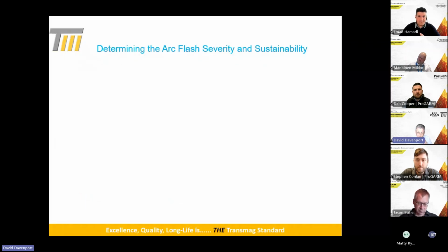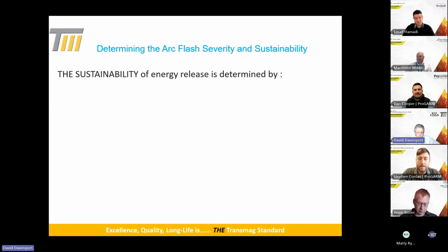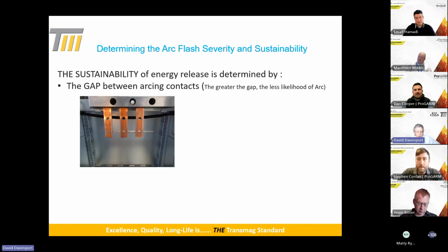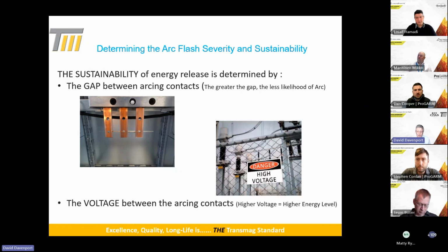So let's talk about the severity and the sustainability of an arc flash, those are the two terminologies. First of all, the sustainability is the gap between arcing contacts. So when the first design is made, whatever that gap is determines how easy it is to get an arc flash to cross across those contacts. And the voltage between the arcing contacts gives you the energy level that you'll get in that sustainability.